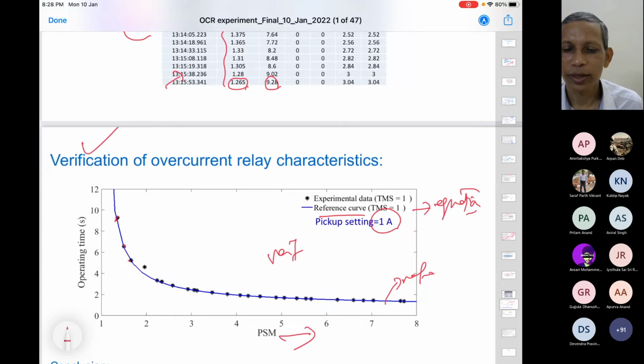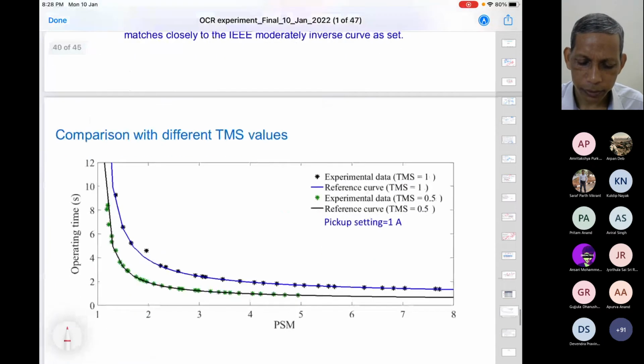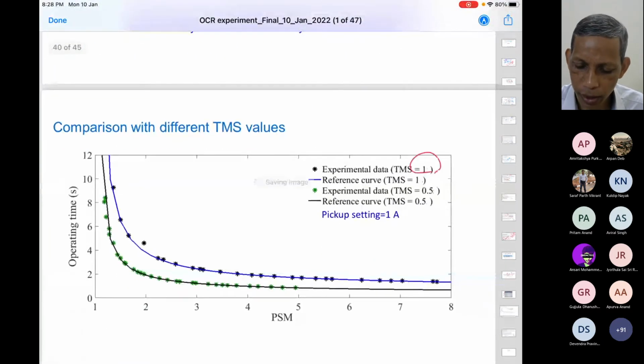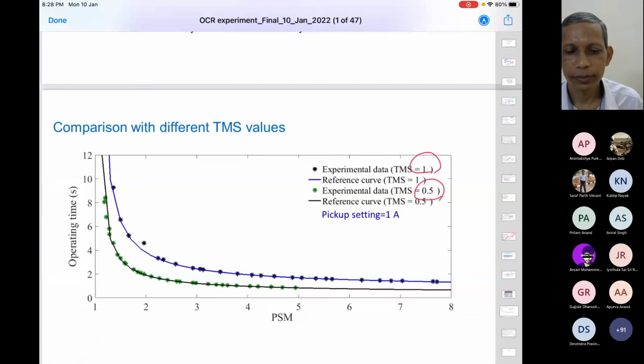We say that the relay is following as per the manual provided by the manufacturer. Agree? This is verified in terms of that also. So we have two TMS now, 1 and 0.5. And the 0.5 TMS is multiplied to the equation, so the lower curve is 0.5. We verified with those two settings also, and they are almost in agreement with the reference, and the reference is nothing but from the equation.